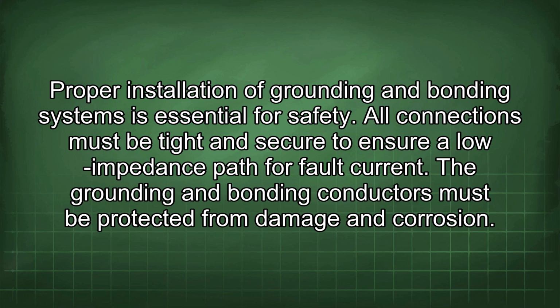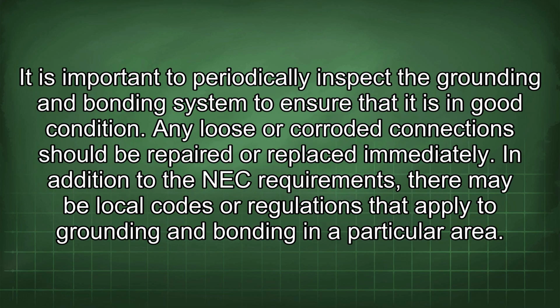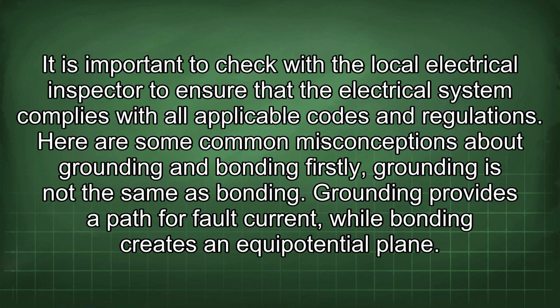The grounding and bonding conductors must be protected from damage and corrosion. It is important to periodically inspect the grounding and bonding system to ensure that it is in good condition. Any loose or corroded connections should be repaired or replaced immediately. In addition to the NEC requirements, there may be local codes or regulations that apply to grounding and bonding in a particular area. It is important to check with the local electrical inspector to ensure that the electrical system complies with all applicable codes and regulations.